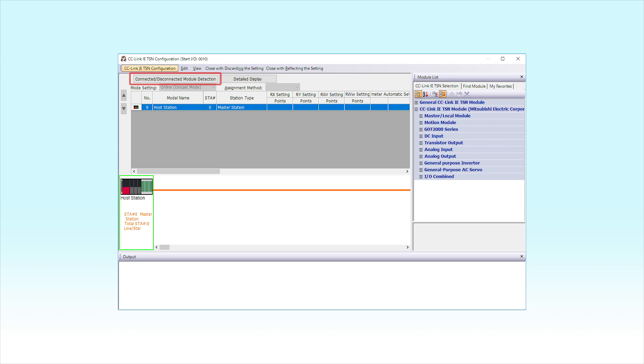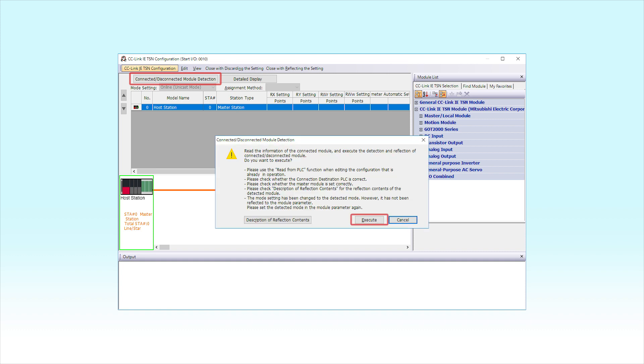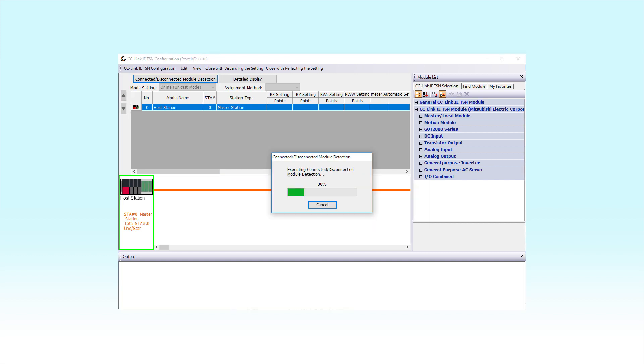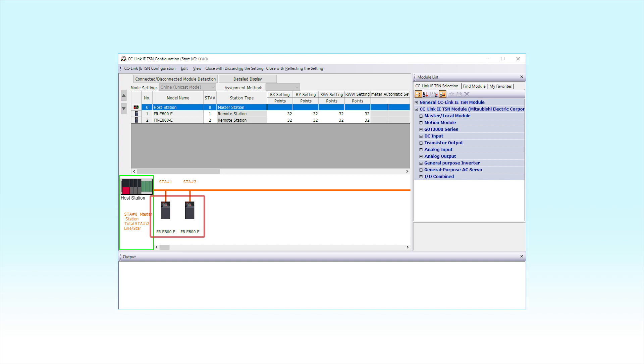Click the Connected, Disconnected Module Detection tab in the CC-Link IE-TSN Configuration window. Then, click the Execute button. FR-E800E will appear on the screen when it has been successfully detected.